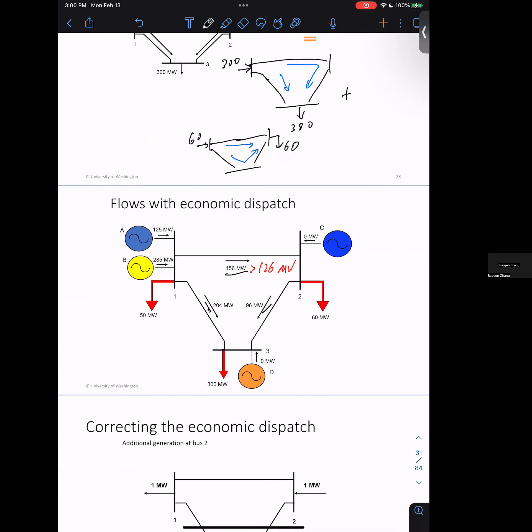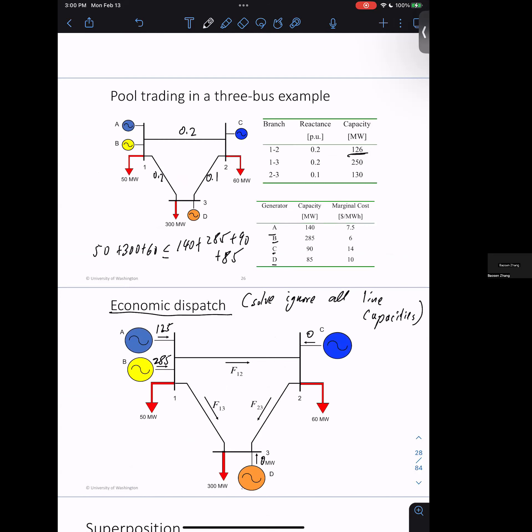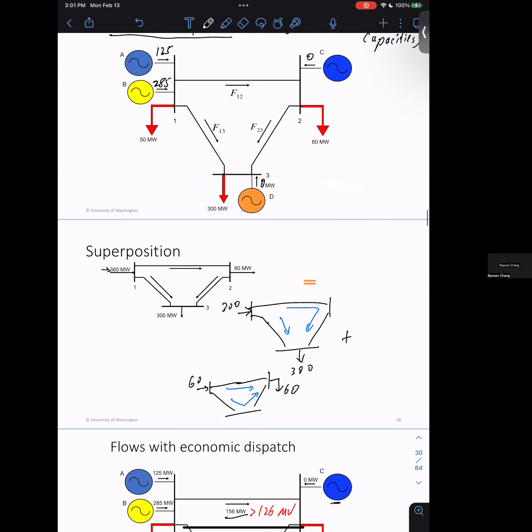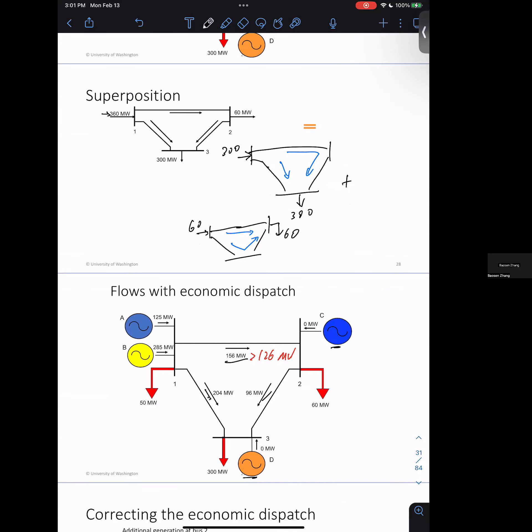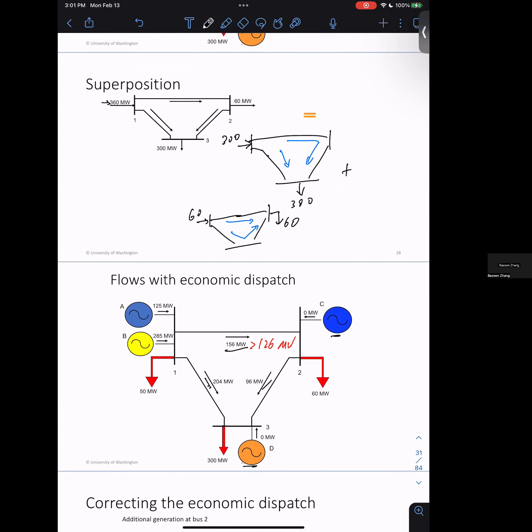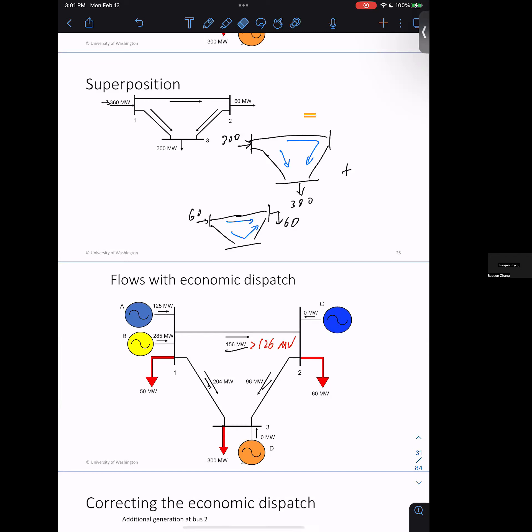To correct this flow, you have two choices. You cannot generate more at generator A since we're already over the line limit. You have to either use generator C or generator D. You look at the cost and consider each option. If you generate more at D, let's see what happens — one megawatt injected at bus two breaks up into two paths.